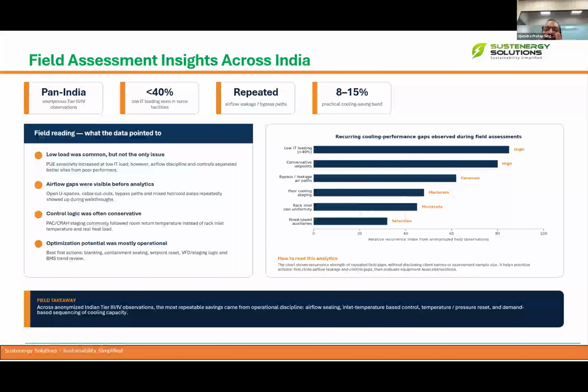Then we found that the airflow gaps were visible before doing any analytics, because once you enter the data centers and start doing measurements, we come to know there is a gap in the airflow. You can find many cables obstructing the path of the airflow, so we need to take them out, because with the passage of time people keep putting in cables and they obstruct the path. The flow of air gets diverted and you don't get proper air at all the racks.